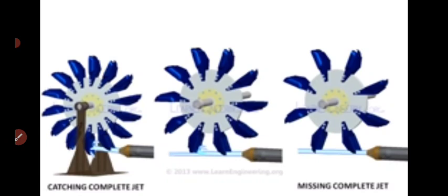The most vital component of the Pelton wheel is its bucket. Buckets are cast as a single solid piece, in order to avoid fatigue failure. The water jet is split into two equal components with the help of a splitter. The special shape of the bucket makes the jet turn almost 180 degrees. This produces an impulsive force on the bucket. The force so produced can easily be derived from Newton's second law of motion. A blade outlet angle close to 180 degrees is usually used in order to maximize impulsive force.